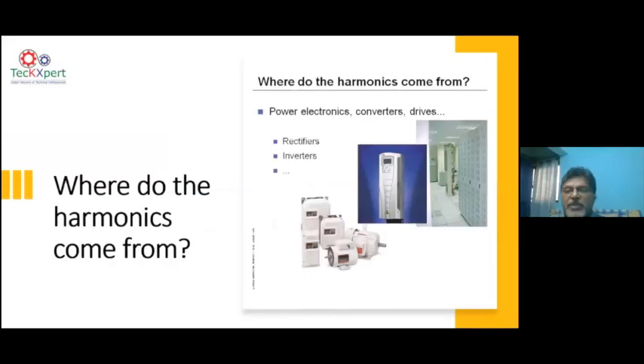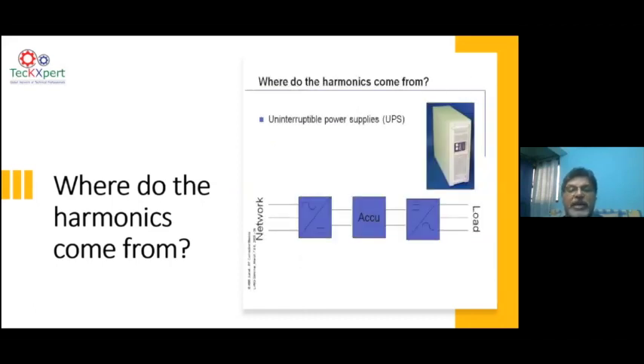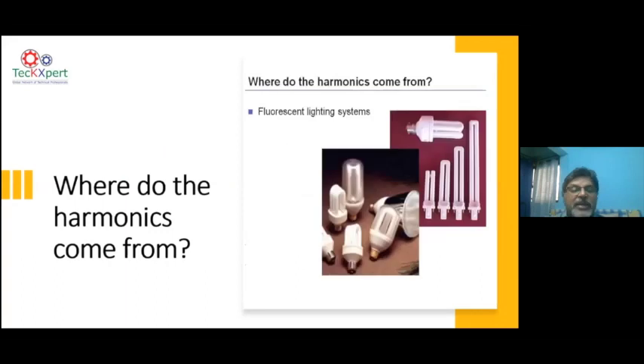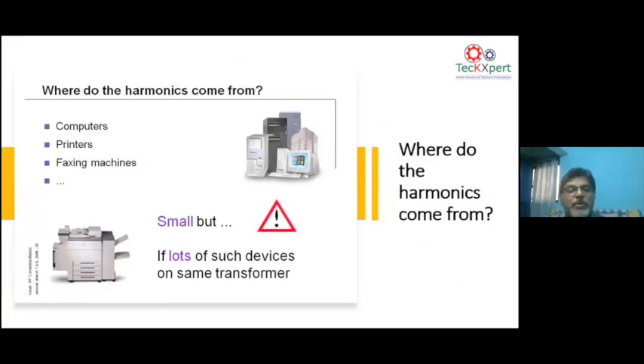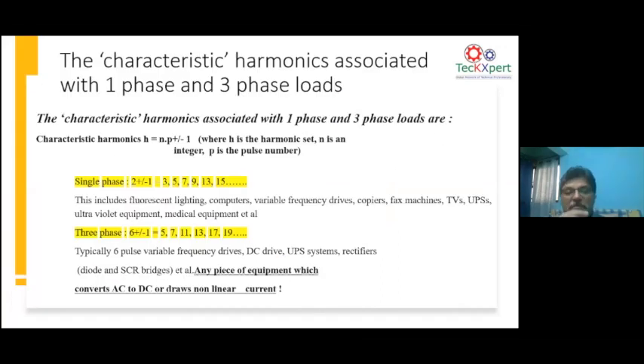Now, as you know, variable frequency drives are one source of harmonics. Again, UPS is another source of harmonics. Then all your lighting, fluorescent lighting or LED lighting, also produces harmonics. Your computer equipment and all office equipment like printers and fax machines produce harmonics. Now, the way you understand the type of harmonics produced by a device is defined by the characteristic harmonic equation.